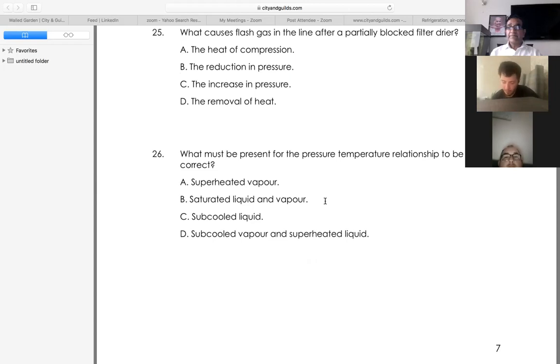Before the expansion valve? Sorry, Jack, was that the mixture before the expansion valve? No, 80-20 is after the expansion valve. Before the expansion valve, we want 100% subcooled liquid. We don't want to send gas to the expansion valve, of course not. We wasted the energy. That'd be a bad system. We wasted the liquid, which would have absorbed more heat in the evaporator.